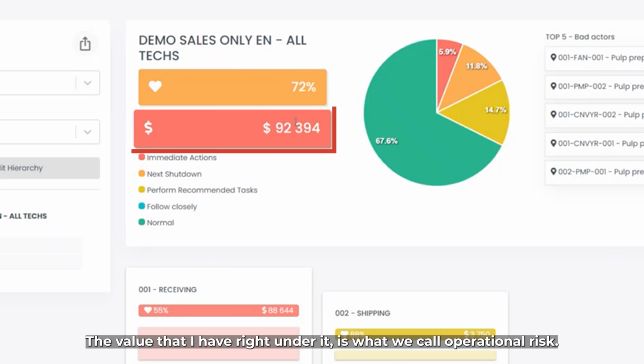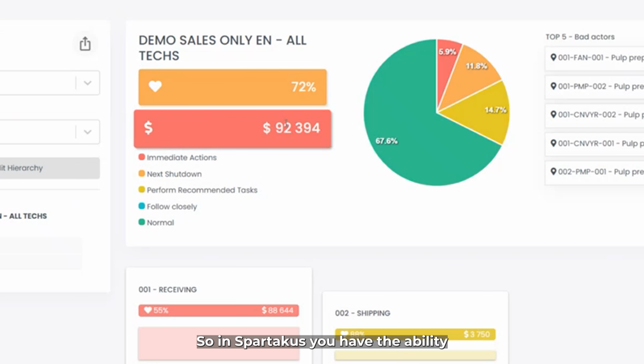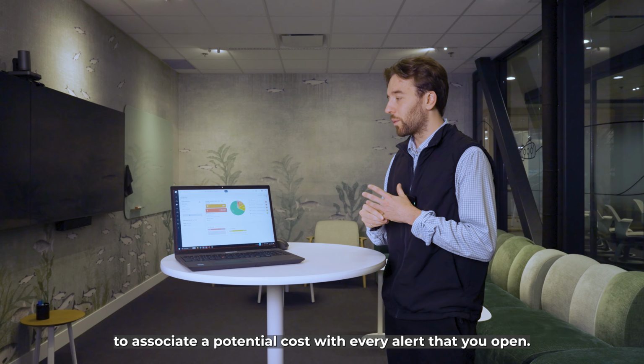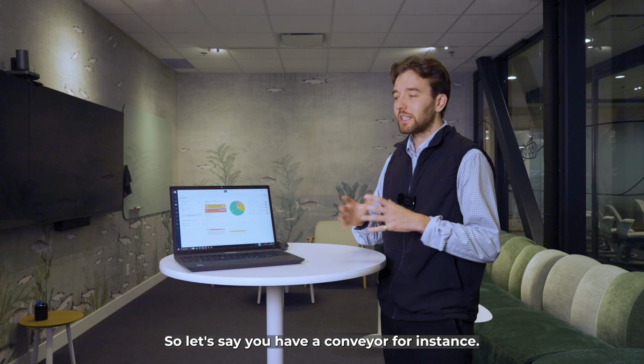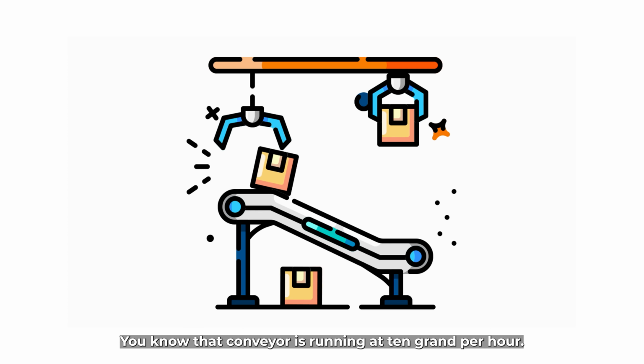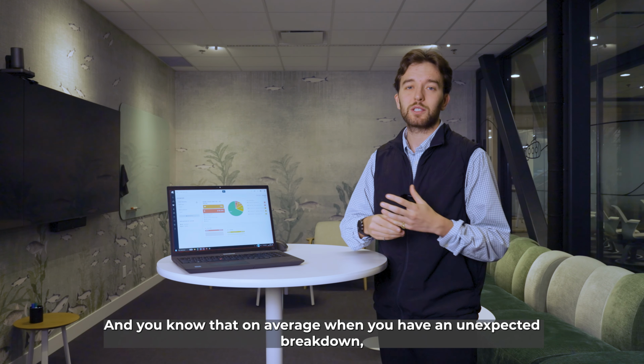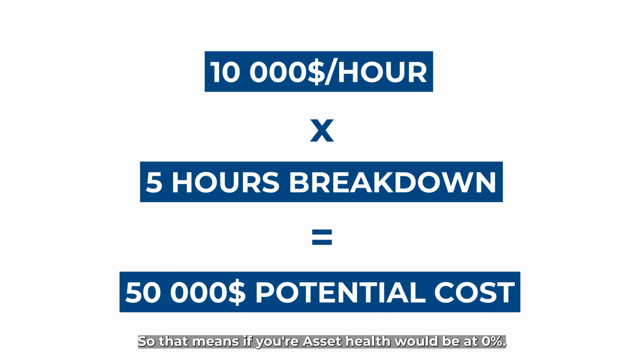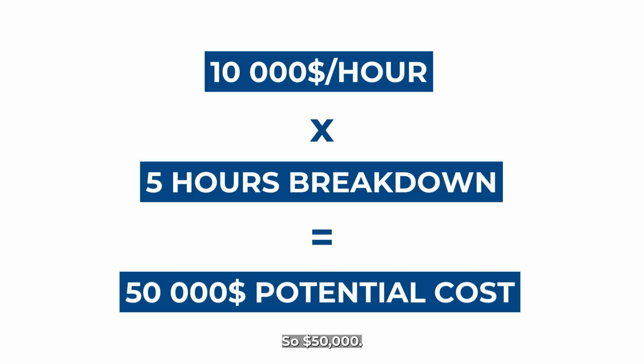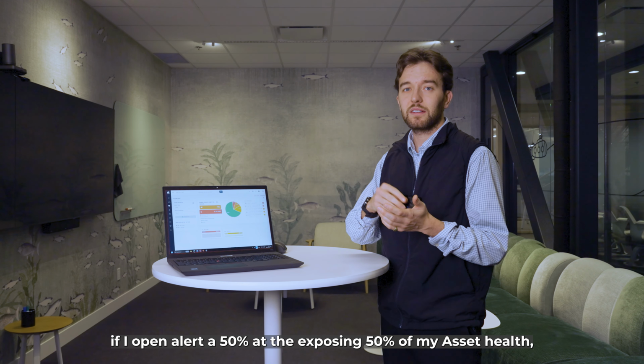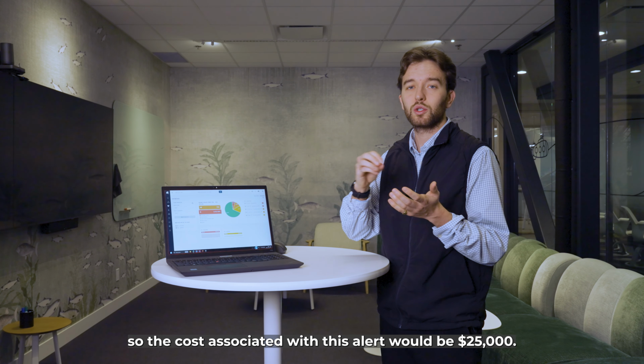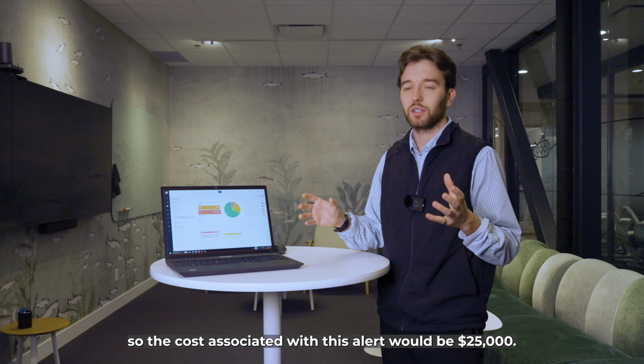The value that I have right under it is what we call operational risk. In Spartacus, you have the ability to associate a potential cost with every alert that you open. Let's do a basic example. Let's say you have a conveyor, for instance. You know that conveyor is running at 10 grand per hour, and you know that on average, when you have an unexpected breakdown, it usually is stopped for 5 hours. So that means if your asset health would be at 0%, you would have a total potential cost of 5 times 10 grand, so $50,000. With that being said, if I open an alert of 50%, I'd be exposing 50% of my asset health. So the cost associated with this alert would be $25,000.